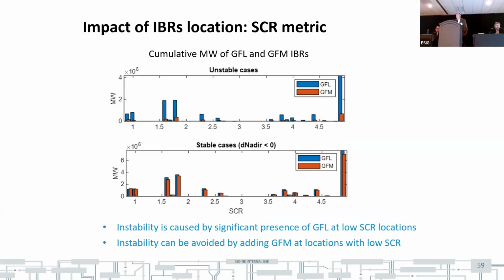Okay, that graph illustrates typically the same result with different metrics. The horizontal axis shows the short circuit ratio where inverters are located. On the top graph, that is the statistic for all unstable cases. And the pattern is pretty clear. Blue bars show the total amount of megawatt for grid following inverters. And if you have prevailing inverters with grid following control, you have instability. On the opposite, the bottom plot shows if you have a proper combination of grid following and grid forming inverters in a location with low short circuit ratio, stability is preserved.